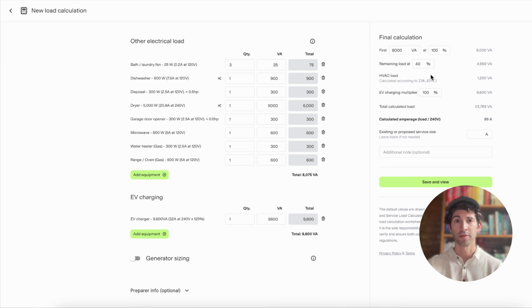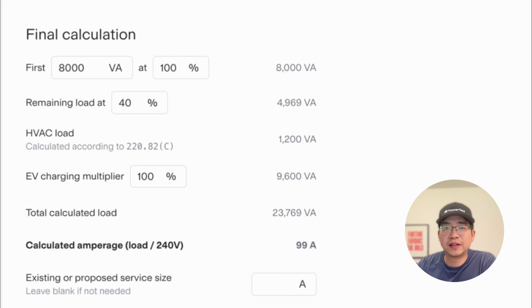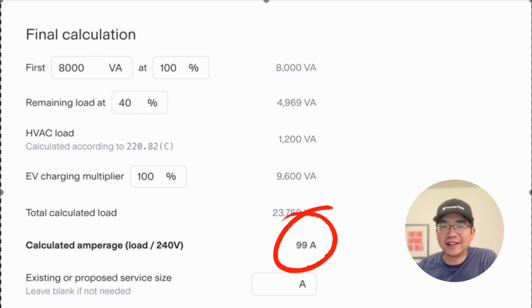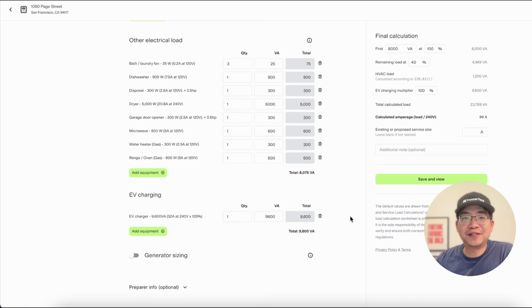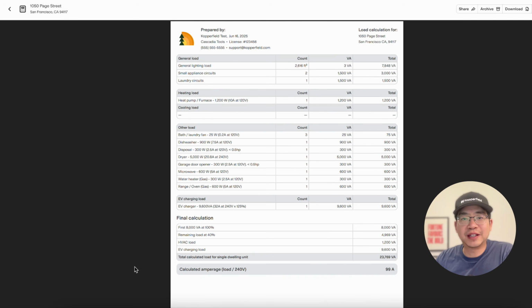It's extremely rare, but if you do need to adjust the percentage or adjustment, you can customize it to meet your local AHJ requirements. Now, with everything accounted for, our total adjusted load comes out to 99 amps. The 100 amp panel is good to go after all. No need to upgrade. Nice. The customer is going to like that. And you've got a clean and professional PDF ready to submit for a fast approval from your AHJ.